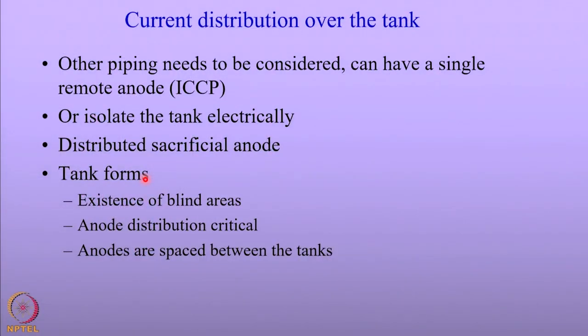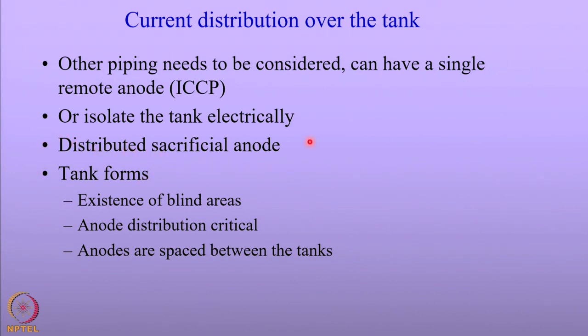The current distribution over the tank is equally important. There are cases where other pipings are considered, especially for buried tanks where the pipings are part of the de-tanking process. You can have a single remote anode that will take care of the cathodic protection of the tanks, or isolate the tank electrically and confine the cathodic protection only to the tank.